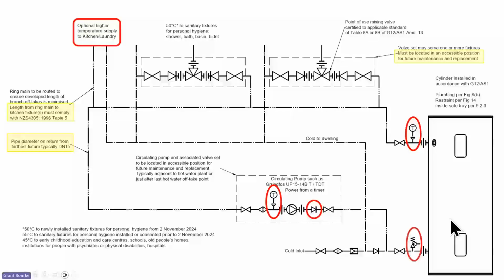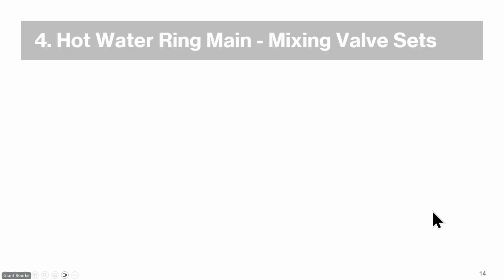The final thing we need is some pressure relief somewhere in the system. We're obviously going to heat up this pipe, and it's just like when you heat up the water heater, you need to have the pressure relieved somewhere. Most systems you can use the expansion control valve in order to relieve the pressure, but you just need to be a bit mindful of where you place it, and we'll look in the drawings about that as we go through. So that's the standard high temperature hot water ring main mixing valves at each offtake point.